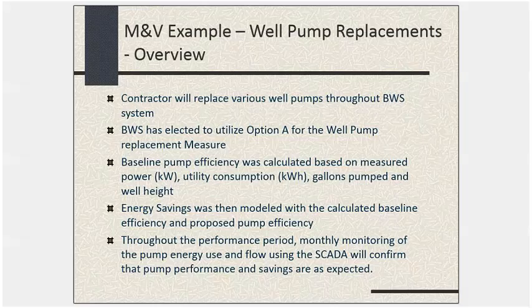Yeah, so the way we actually set up the model, you don't actually need to do that. Given that at these sites 90 plus, 95, 99% of the electrical usage is from those pumps, it's very easy to see when one stage is on and one stage is off based on the flow data. You're going to go up from 1.5 MGD to 3 MGD, so you can tell immediately when another pump turns on. You can use that as your guideline for when one pump is running versus two pumps running. Because there's no variability, they're just on or off, it's really easy to tell exactly what's happening at any given point given the SCADA data. You have what we call a very chunky load profile, it's on or it's off, and when it comes on, it's on in a big way.